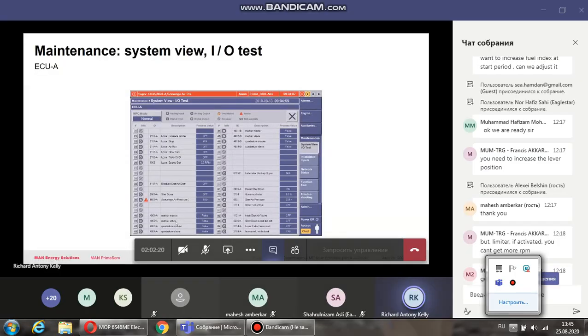Yes. The tacho system has to have 4 valid signals. Can you remember the two encoders, encoder A and encoder B? They have to have the 4 valid signals. So they need to have marker master, marker slave, quadrature 1, quadrature 2 in your A system. If you invalidate one of those, then you're inadvertently invalidating the whole tacho system.